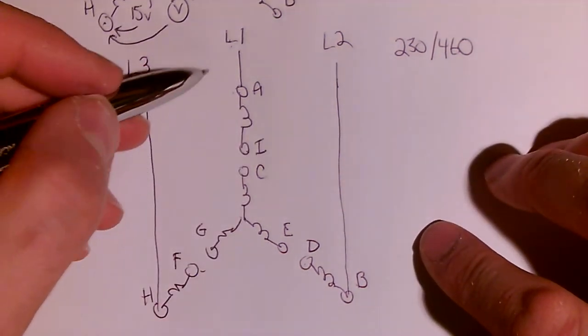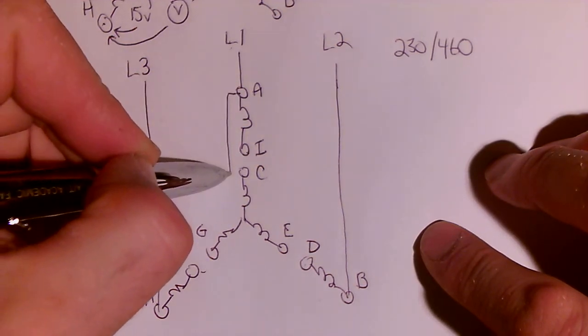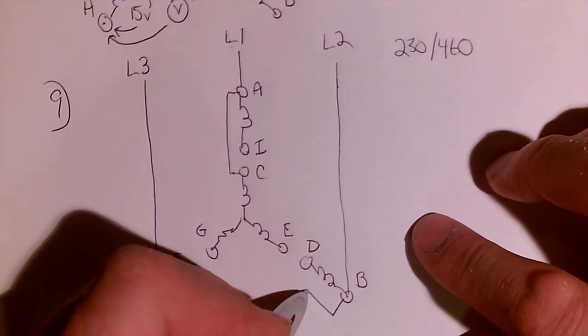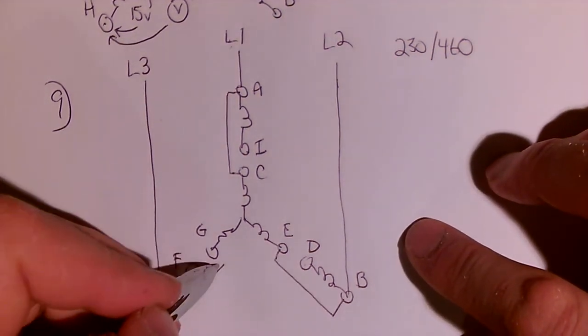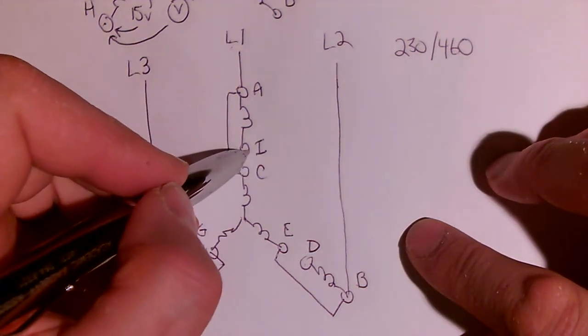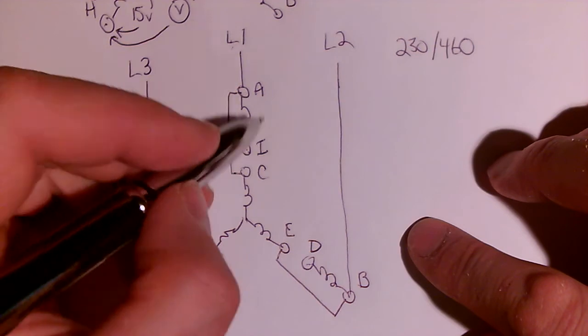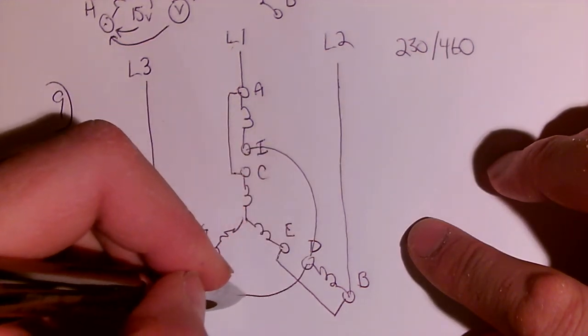And we have to connect this for low voltage. So A is also going to connect to C. Because we want these in parallel. B is going to connect, in this case to E. And H is going to connect to G. And then T4, T5, and T6 are all going to connect together. So you need a jumper from I to D. And a jumper from D to F.